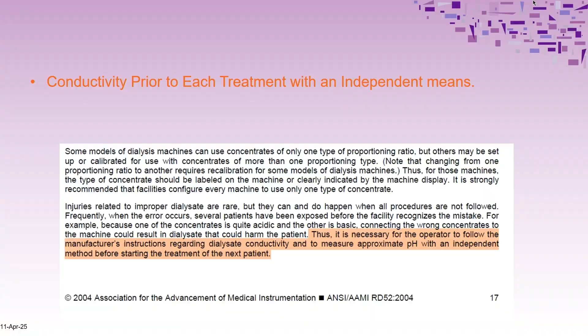This is necessary for the operator to follow the manufacturers' instructions regarding dialysate conductivity and to measure approximate pH with an independent method before starting the treatment on the next patient. This is a very old picture, but this is where that requirement also came from.